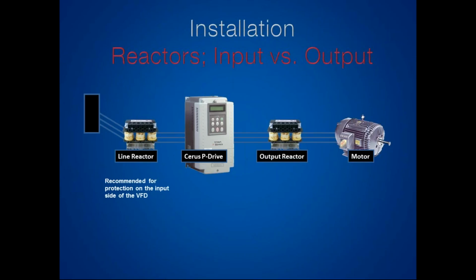So we've got our line reactor, we've got our drive, and then we've got our output reactor, okay? An output reactor is protecting our motor on the output side of things. The output reactor is cleaning up the output side of the drive. Now, typically in HVAC applications, we don't need an output reactor.